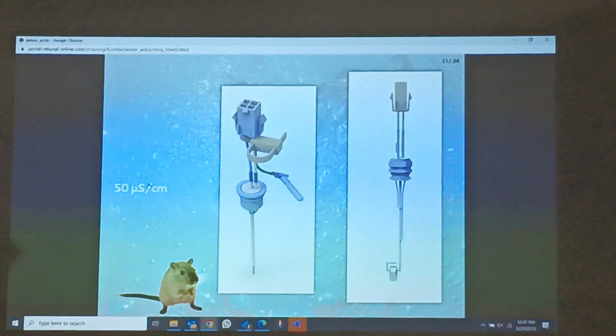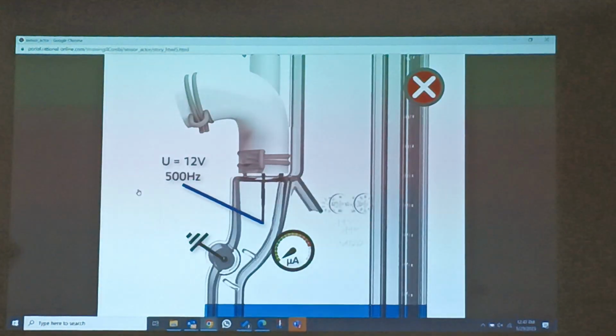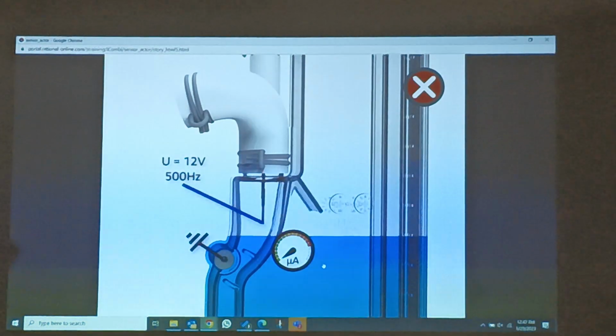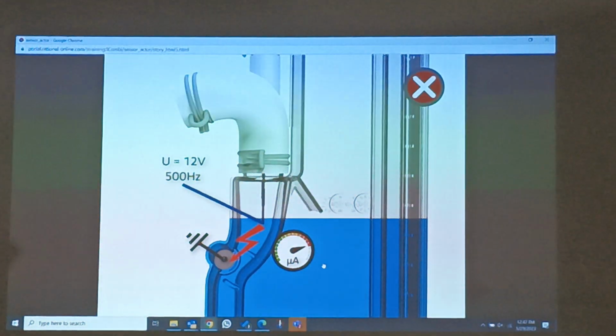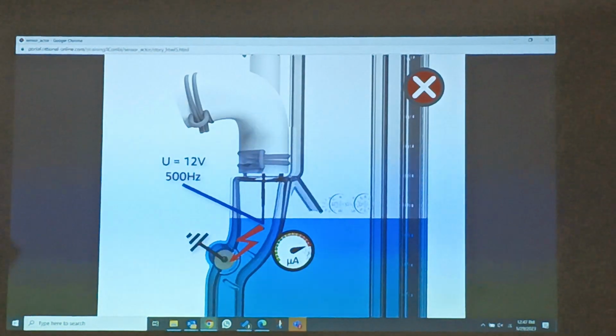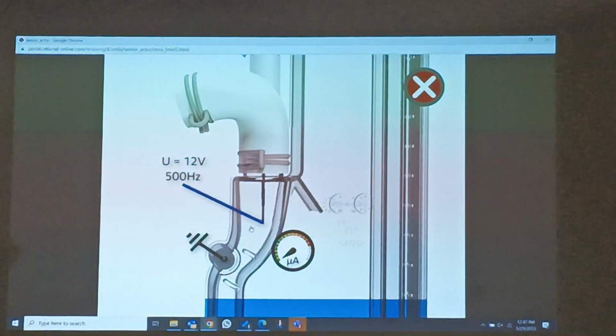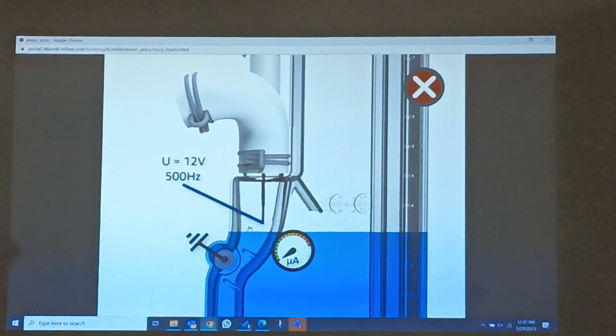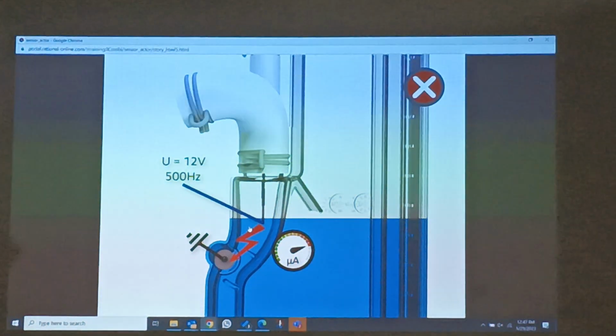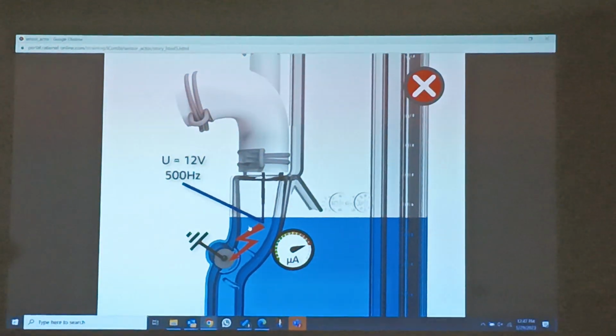Use the new one. Then here we have the water level sensor. Make sure the water conductivity should not be less than 50 microsiemens. Here we are getting the microampere. It's getting a supply from here of 12 volt, 500 hertz. You need a special meter to check. I think you don't have one which can measure up to 500 hertz.